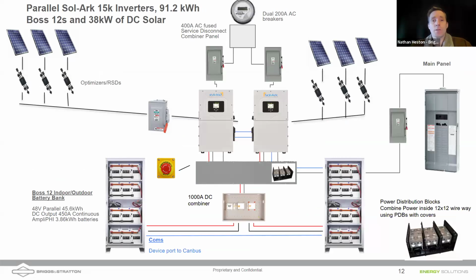What I like about this configuration, Daniel, is that we're showing the solar feeding into the inverters, but we're showing two paralleled inverters here. And what's the advantage there? More power. Absolutely, more power. Instead of being limited to 200 amps of pass through from the grid, now we can pass 200 amps through each of those inverters.